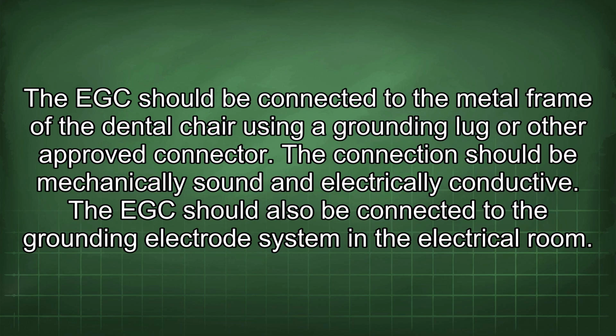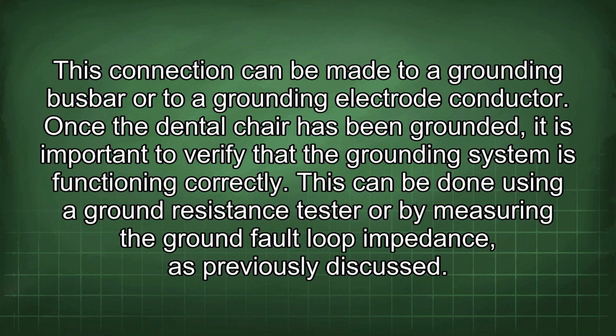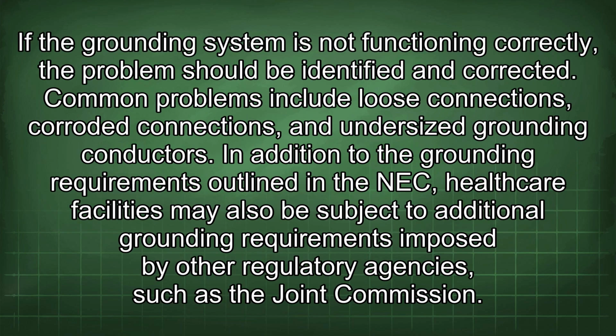The EGC should be connected to the metal frame of the dental chair using a grounding lug or other approved connector. The connection should be mechanically sound and electrically conductive. The EGC should also be connected to the grounding electrode system in the electrical room. This connection can be made to a grounding busbar or to a grounding electrode conductor. Once the dental chair has been grounded, it is important to verify that the grounding system is functioning correctly. This can be done using a ground resistance tester or by measuring the ground fault loop impedance, as previously discussed. If the grounding system is not functioning correctly, the problem should be identified and corrected. Common problems include loose connections, corroded connections, and undersized grounding conductors.